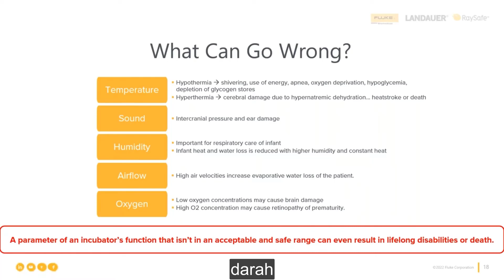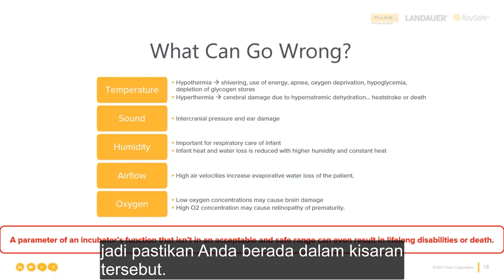So it is important to make sure that the air is humid and not too dry. Airflow. Airflow helps circulate warm air throughout the cabin of the incubator. But high air velocities often result in evaporative water and heat loss for the patient. So making sure you're in that range is critical for those patients. Again, how it ties back to humidity and temperature.